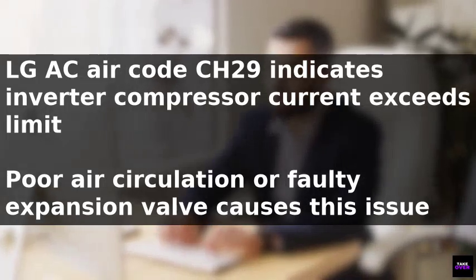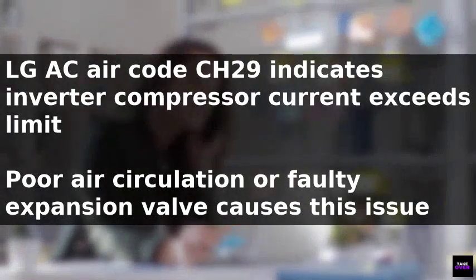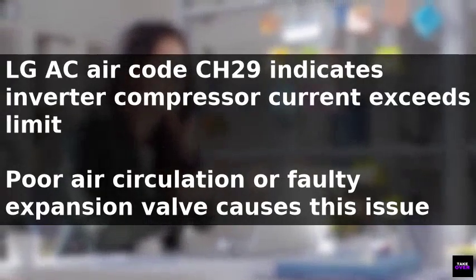The LG AC error code CH29 indicates that the inverter compressor current exceeds the allowed limit. This issue can be caused by poor outdoor unit air circulation or a faulty outdoor unit electronic expansion valve. To fix this problem, start by checking the outdoor unit heat exchanger.